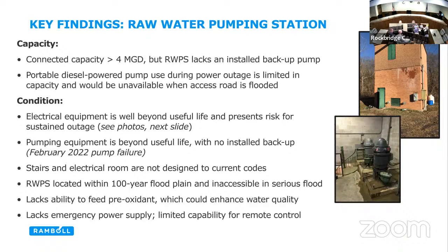A couple other items. The pump station is located within the 100-year floodplain. For staff, during flood events, it can't be accessed. It lacks the ability to feed some chemicals, pre-oxidant, which would help to enhance water quality. And again, touching on the lack of emergency power supply, there is no backup generator on site, and there's limited capability currently for remote control and observation.